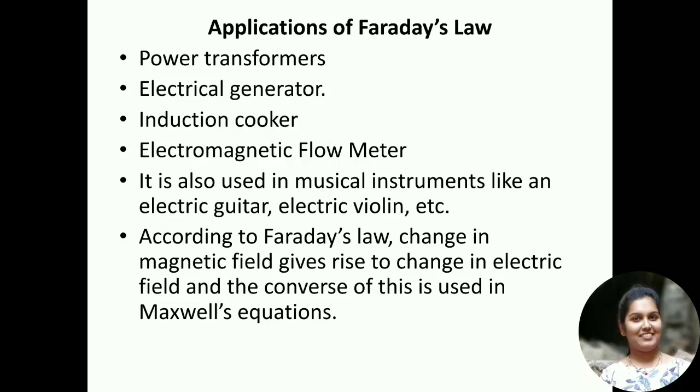The next application of Faraday's laws is the electromagnetic flow meter. The electromagnetic flow meter is used to measure the velocity of certain fluids. When a magnetic field is applied to an electrically insulated pipe in which conducting fluids are flowing, then according to Faraday's law, an electromotive force is induced in it. This induced EMF is proportional to the velocity of the fluid that is flowing.